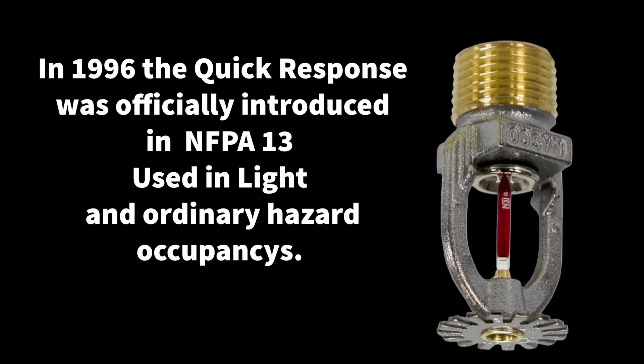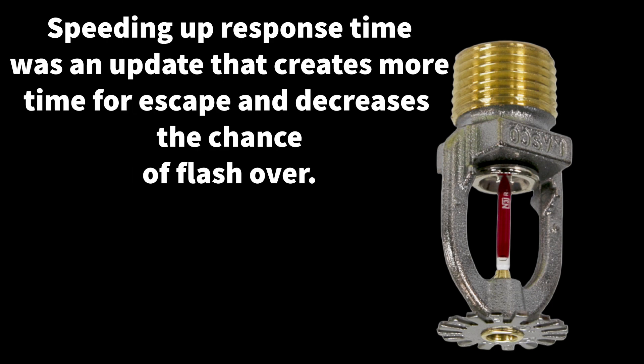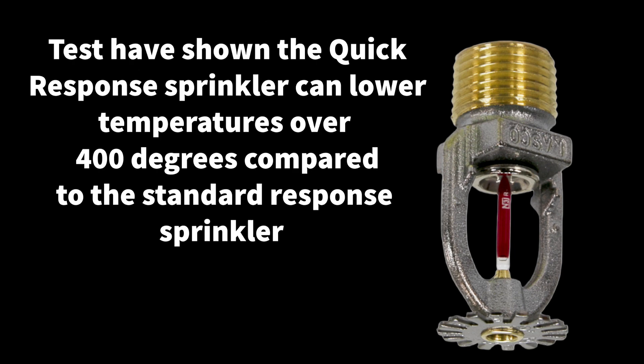In 1996, the quick response was officially introduced in NFPA 13, used in all light hazard occupancies and also in ordinary hazard occupancies. Speeding up response time creates more time for escape and decreases the chance of flashover. Tests have shown the quick response sprinkler can lower temperatures by over 400 degrees compared to the standard response sprinkler.